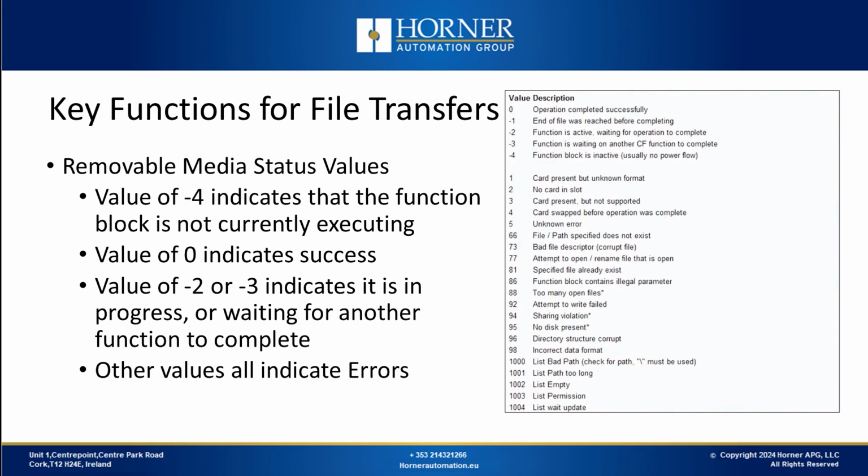If you get a value of 0 for your status register, then the file transfer was successful. If you get a value of -2 or -3, this means the function is active and waiting on another function to complete. All other values are errors.